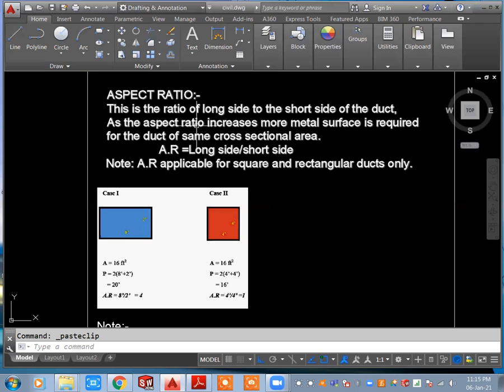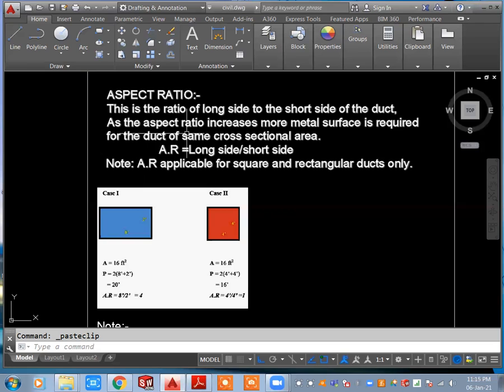The aspect ratio is the ratio of the long side to the short side of the duct. As the aspect ratio increases, more metal surface is required for the same duct cross-section area. For example, if you have one rectangular duct and one square duct with the same cross-section area, the cost is different and the friction loss and pressure loss are also different.